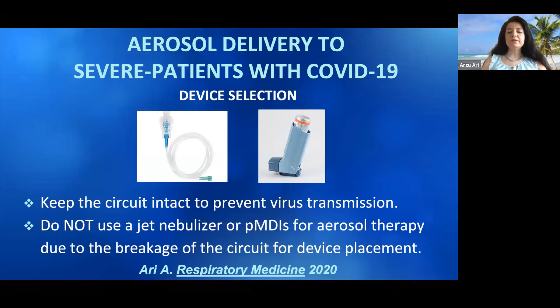So what are we going to use? I recommend using the mesh nebulizer in this type of situation because they can stay in line up to 28 days. The reservoir design here actually eliminates the breakage of the circuit. You place the nebulizer prior to the humidifier and you can keep it there for 28 days without breaking the circuit. And you should also keep the reservoir cap closed here after each use.